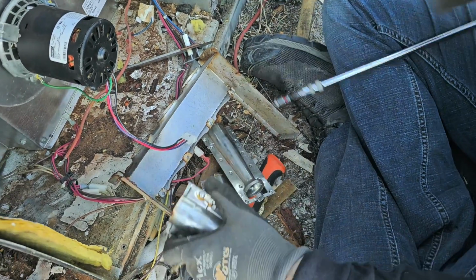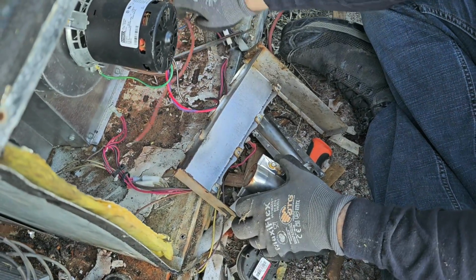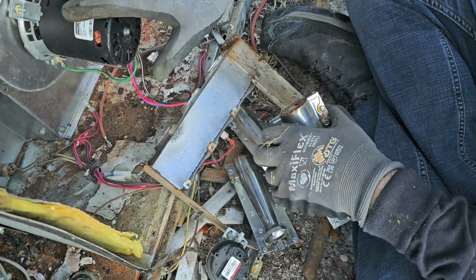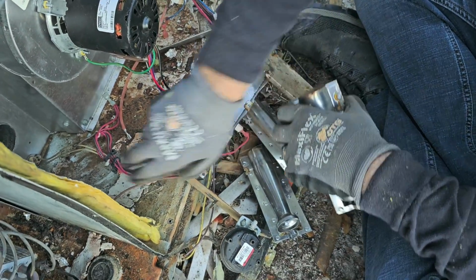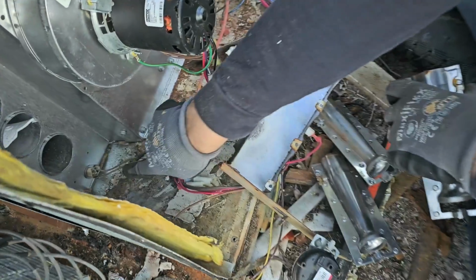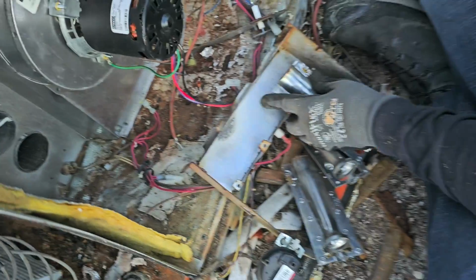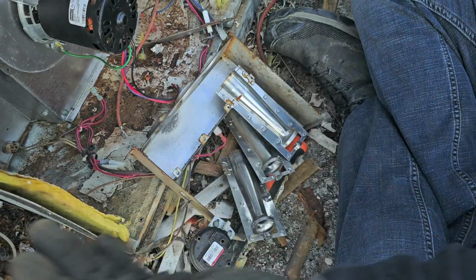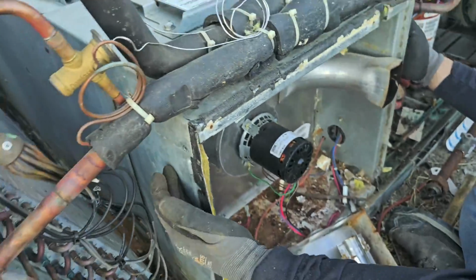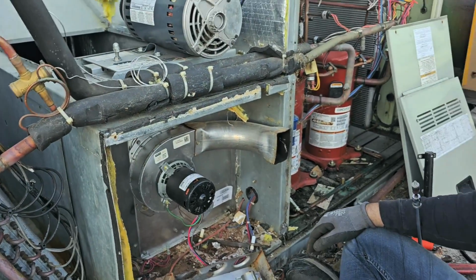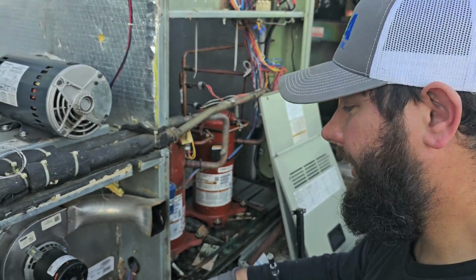All right, put these back in. I got all the wires ran through. Got the inducer motor put back on with the little flue pipe, and then I've got the limit switch down here in its place. I'm gonna put these burners back together. I got the screws put on both sides, and we're almost ready to put the blower housing back in and start it up.